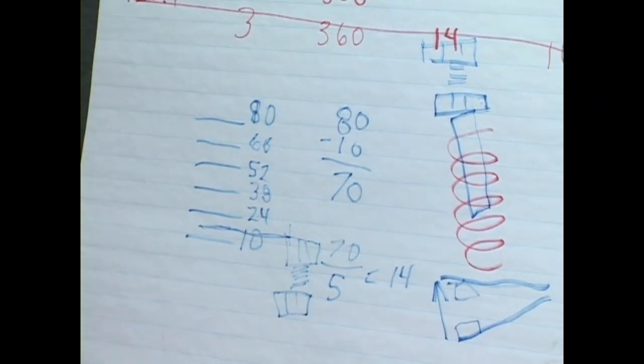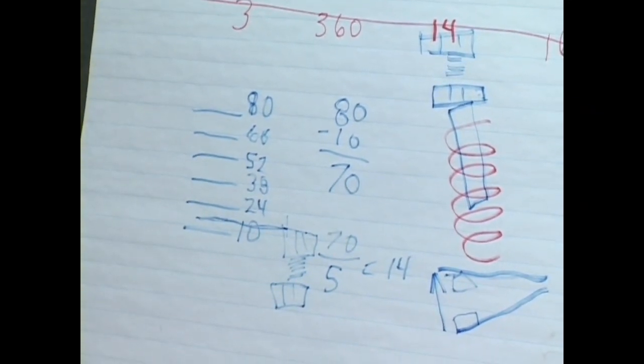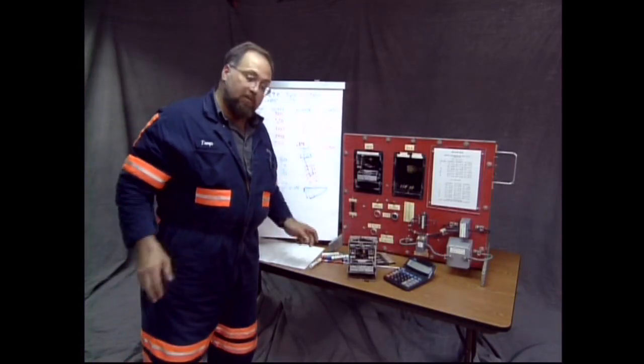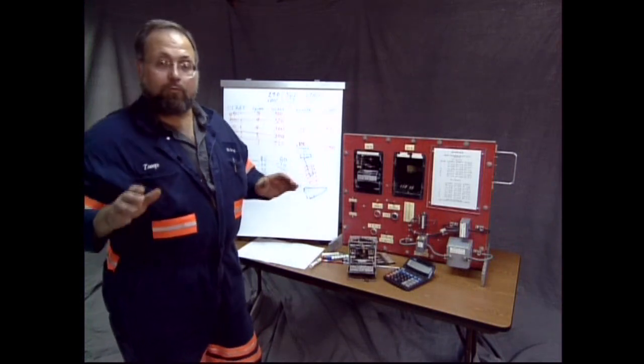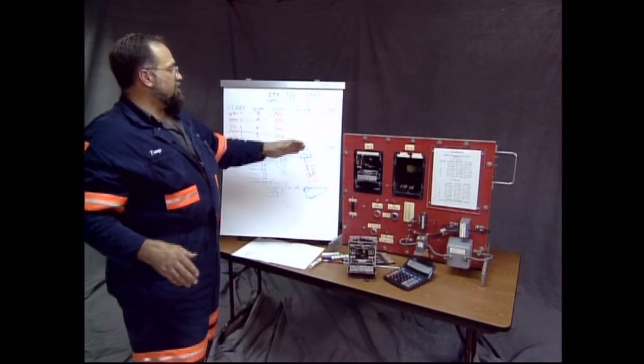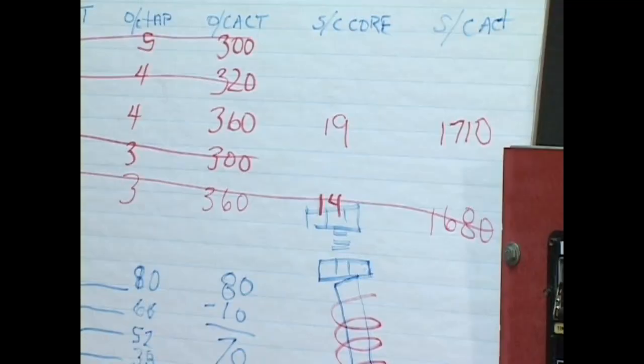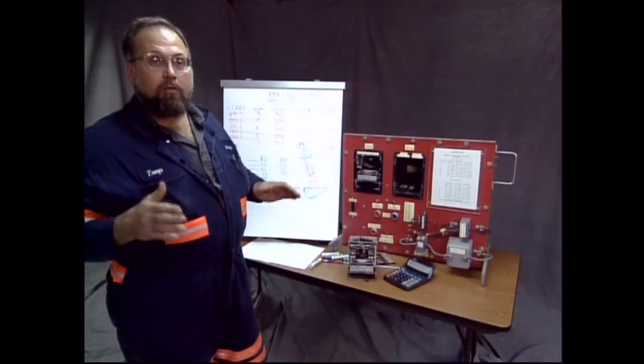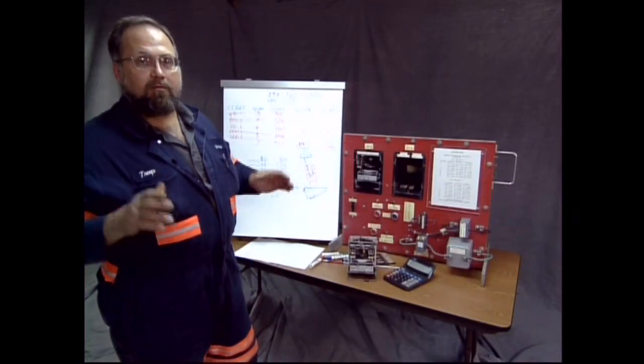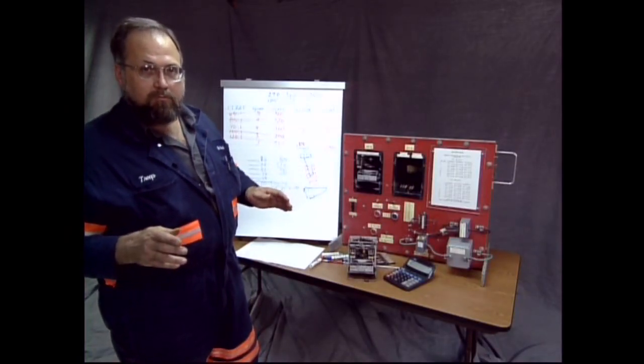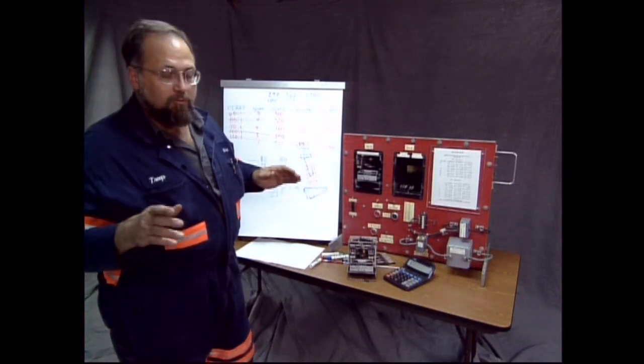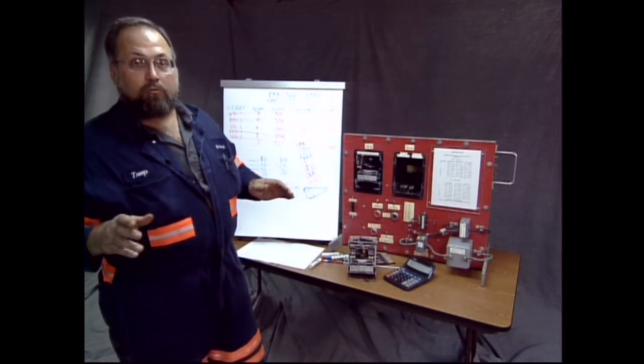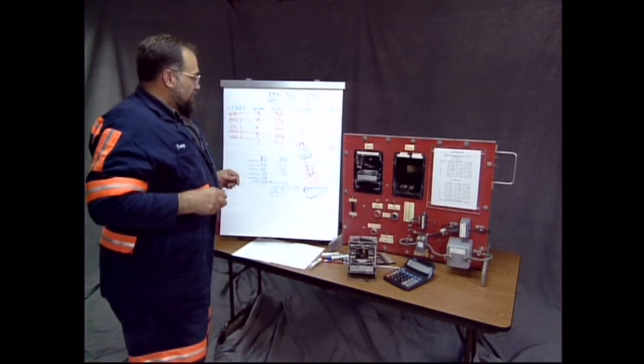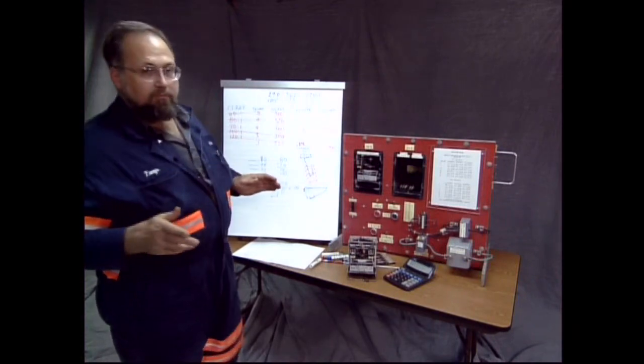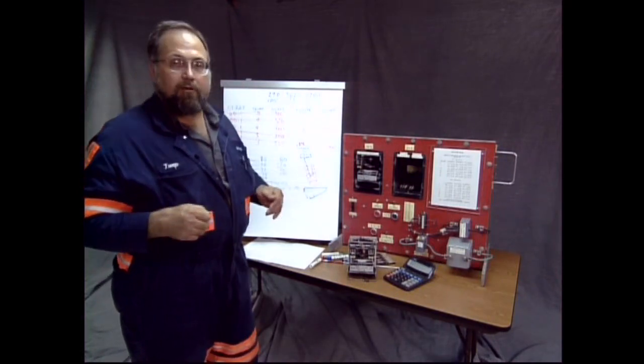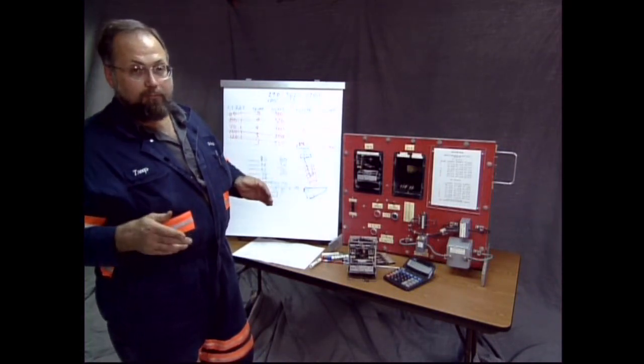Tighten the set screw. Again, that's not an exact science. That's not going to be perfectly to trip at 1710 amps. It'll be close. Don't go above it. Don't go way above it. Stay close. If you're unsure, set low. Lower's better. Setting one too low won't get you a violation and won't cause a mine fire. Setting one too high could do both.